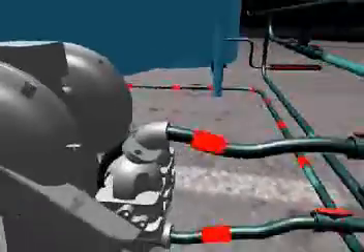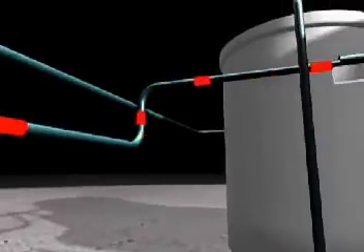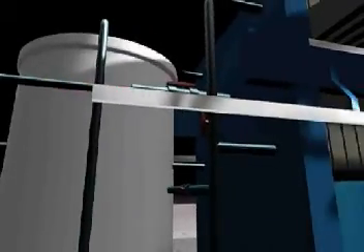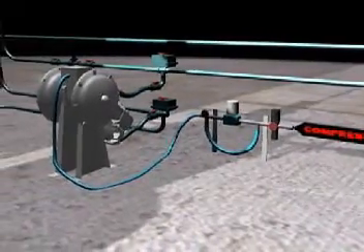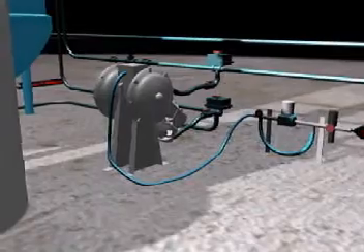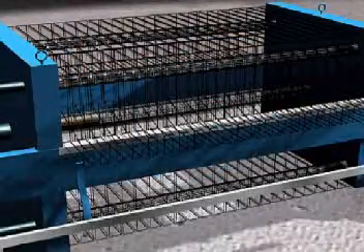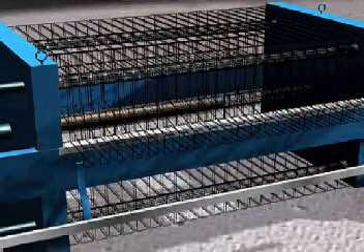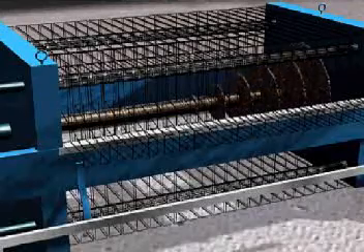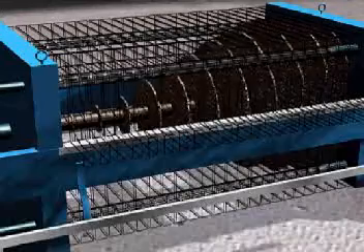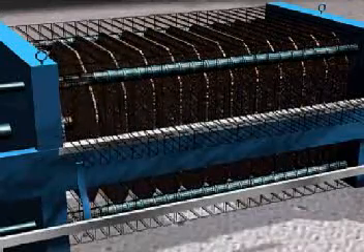With this phase, the de-watering of the sludge begins. The sludge pump works through several increments of pressure of sludge transferred to the filter press. This is controlled through monitoring the sludge pump with a stroke monitoring device and transducer controlled by the PLC. The sludge in the treatment tank contains 95 to 99 percent water, and on being pumped to the filter press, the solids are retained in the chambers of the filter plates, while the filtered water is discharged through the corner discharge ports and collects in an inspection tank.